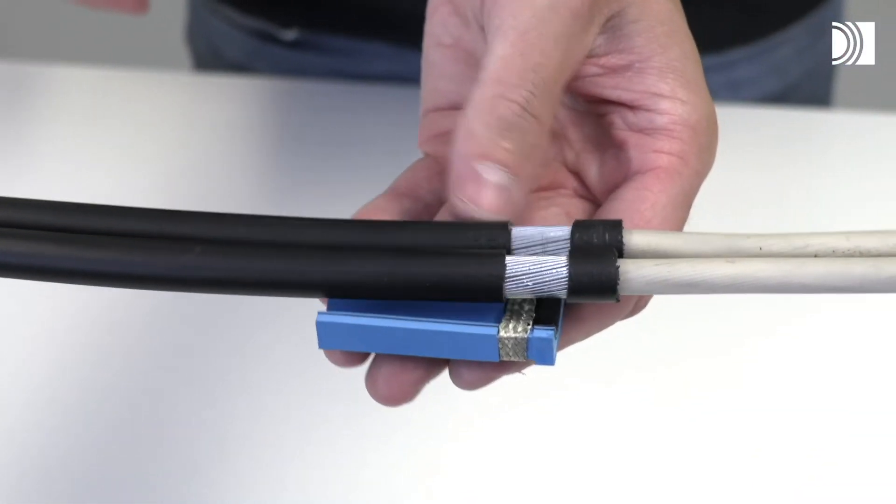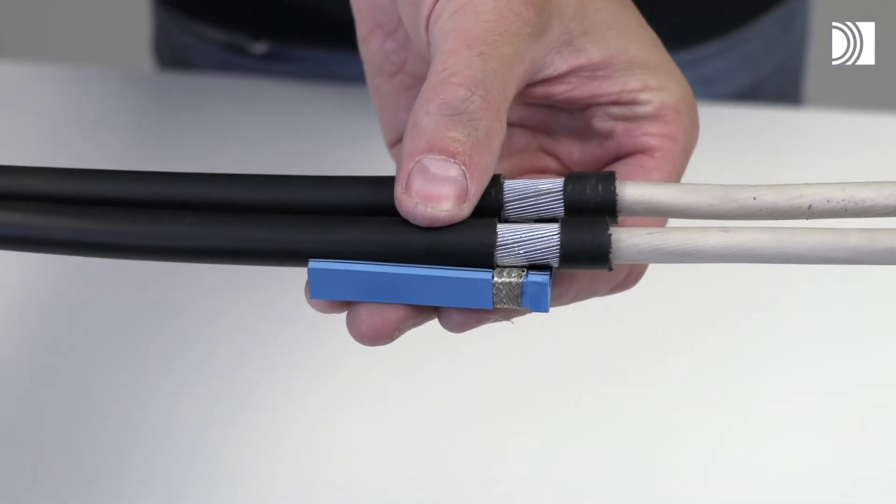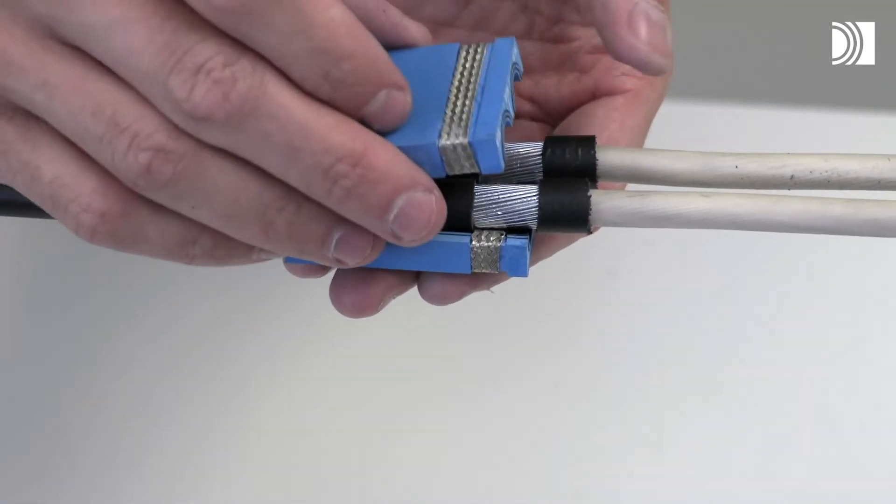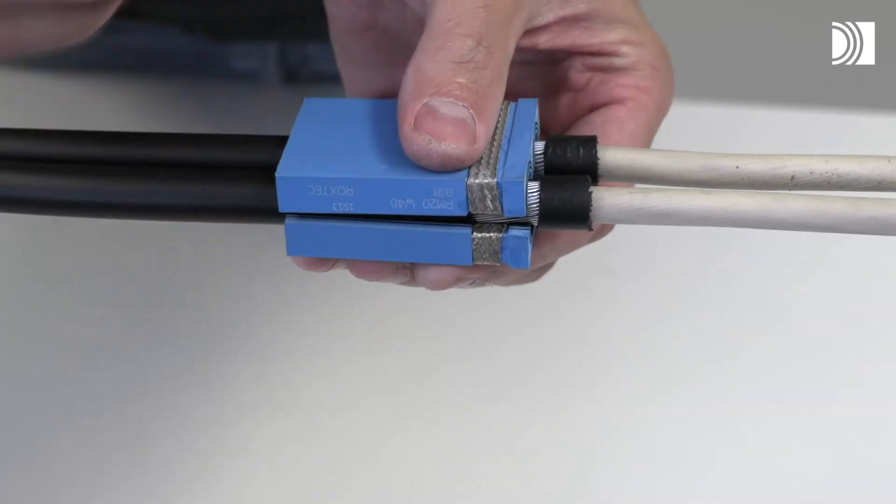Note that the armored cables are correctly prepared when a part of the jacket is removed, the cut matches the braid section of the module, and the armor extends beyond the edge of the module.